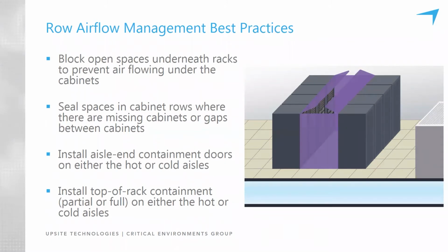Installing aisle end doors. This prevents the wraparound mixing that will occur at the aisle ends if doors are not used. So doors are very important, and they're available in many designs from a variety of manufacturers, and we'll get into greater detail about doors on some of the subsequent slides.